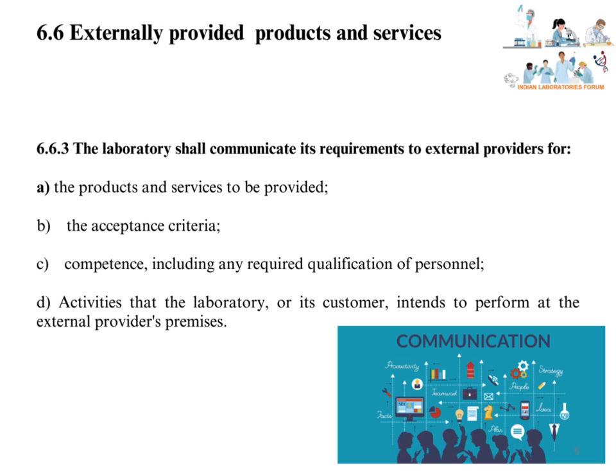The laboratory shall communicate its requirements clearly to external providers. This communication should clearly specify the products and services to be provided — such as chemicals, consumables, equipment, calibrations, qualifications, subcontracting, etc. — along with the acceptance criteria, such as purity and traceability of chemicals, reference standards, acceptance criteria of calibrations, and specification limits of testing. When taking services for qualification of equipment or hiring personnel through an HR consultancy, the laboratory should clearly communicate what expertise or competency is required for the personnel to perform the activity.